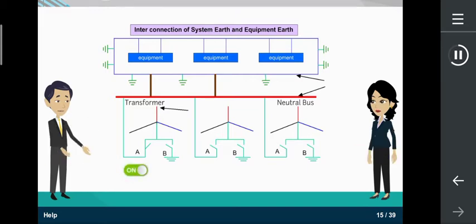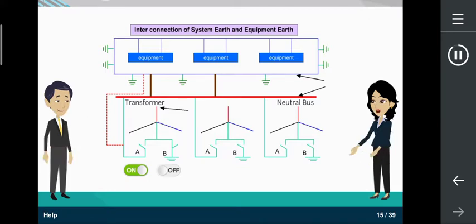Oh, then? Therefore, before putting off switch B to disconnect the power, we will put on switch A first and then put off switch B. Doing this will cause the neutral of the transformer to connect with the mass of Earth through the equipment bus bar. This will allow the power to be disconnected to pit B without disturbing power to the installation, and work can be carried out. This is all about the connection between system earth and equipment earth. That was indeed interesting. Thank you. Pleasure is all mine. Let us further learn about maintenance of earth pits.